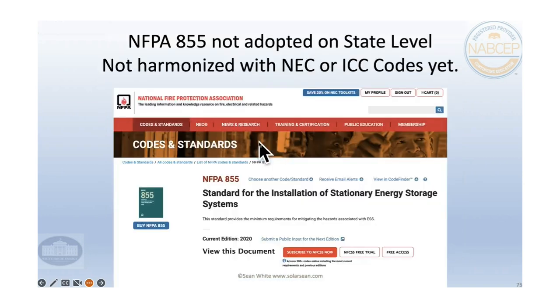There's also a standard, and I don't know of any place that has adopted this NFPA standard. The NEC is the most widely adopted code, but there's lots of different standards. It's NFPA, you can see all their standards. It looks to me like a list of 1,000. I'm not sure if it's exactly 1,000, but there are a lot of standards that NFPA has. This is 855. NFPA 1 is the fire code that competes with the IFC, the International Fire Code. And I think it's like Florida and Maine and a couple other places that have adopted the fire code. But anyway, you can get some good ideas from 855, but it's not something that's usually enforced anywhere except maybe by an insurance company.